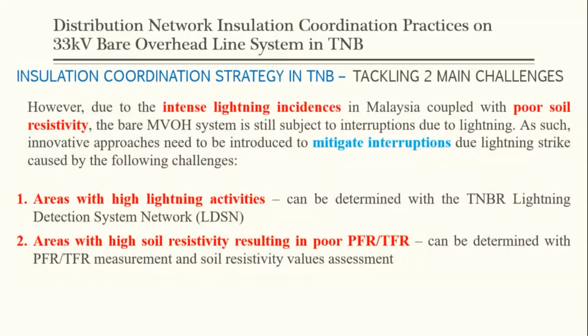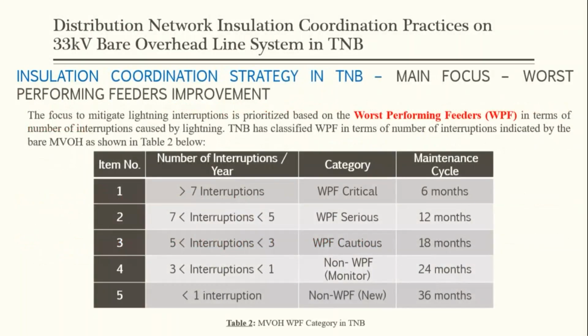The challenges in insulation coordination in TNB is to tackle two main things. First of all, areas with high lightning activities, and secondly, areas with high soil resistivity resulting in poor PFR or TFR. Our main focus is to improve on the worst performing feeders. The focus to mitigate lightning interruptions is prioritized based on the worst performing feeders, in terms of number of interruptions caused by lightning, right? And TNB has classified WPF in terms of number of interruptions indicated by the table below.